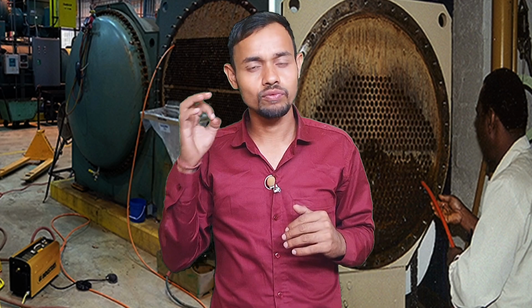Friends, imagine your hotel has a 300 TR water cooled chiller. Okay, after new installation, before descaling, the chiller is doing chilled water at 6 degrees Celsius. Second, good cooling, and third, smooth compressor performance. After 3 to 4 months, the water is stuck at 10 to 12 degrees Celsius and guests are complaining of heat. Okay, electricity bill increases 25%. Compressor overloaded. What does the technician say? The technician says to the engineer, sir, the condenser is choked with scale. If you do not do descaling, the chiller will trip.